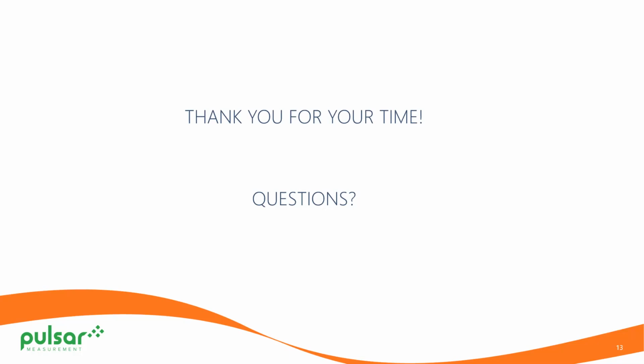So I just see another question pop up here. The difference between DFM 5.1 and flow pulse. Well, the flow pulse is, so you're obviously familiar with the Pulsar flow pulse. It's just different ways we're doing the Doppler technology. The flow pulse is designed more to read flow or no flow. It's not designed to be perfectly accurate. That's not what you're looking for with the flow pulse.